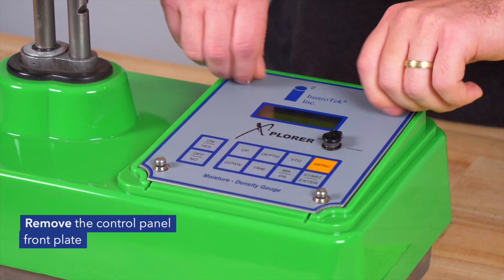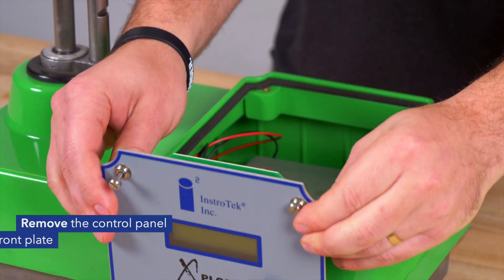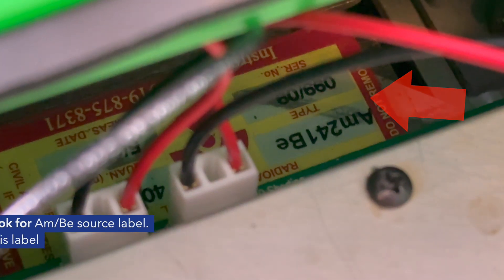Remove the control panel front plate. Look for the Am/Be source label. The source holder is under this label.